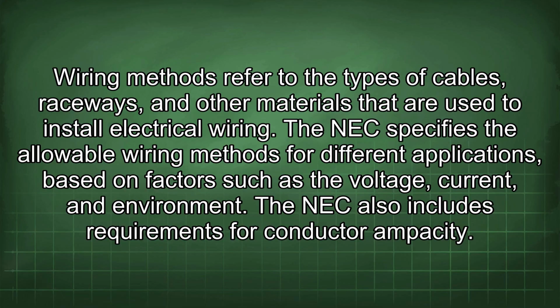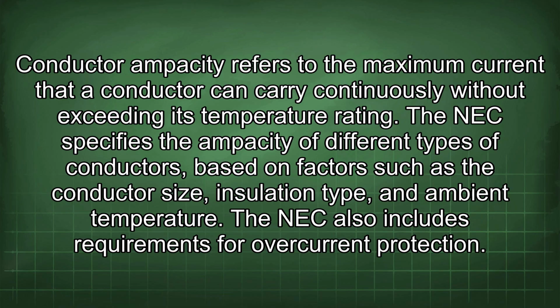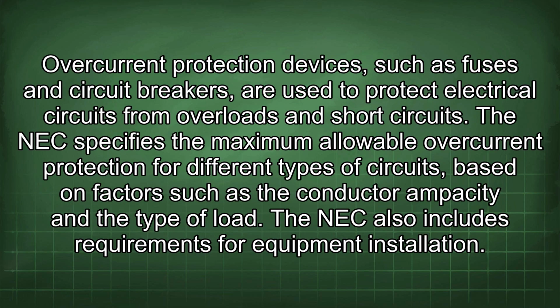The NEC also includes requirements for conductor ampacity. Conductor ampacity refers to the maximum current that a conductor can carry continuously without exceeding its temperature rating. The NEC specifies the ampacity of different types of conductors based on factors such as the conductor size, insulation type, and ambient temperature. The NEC also includes requirements for overcurrent protection. Overcurrent protection devices, such as fuses and circuit breakers, are used to protect electrical circuits from overloads and short circuits. The NEC specifies the maximum allowable overcurrent protection for different types of circuits based on factors such as the conductor ampacity and the type of load.